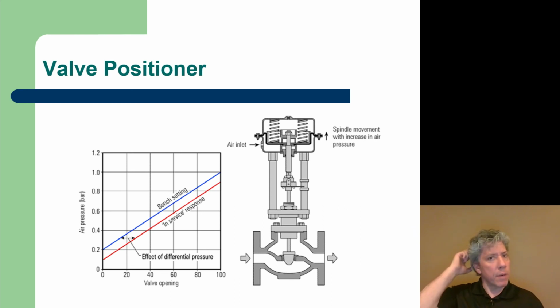Otherwise, they just don't operate very well. Well, I saw this, and I said, okay, I know how to fix this problem. I just removed that 1-inch valve, and I bought a valve that was 2 pipe sizes down. I bought a 1/2-inch valve, reduced it down on either end, put it in the line, and it worked great. Mainly because that valve was the primary restriction for flow in the whole piping system we had.